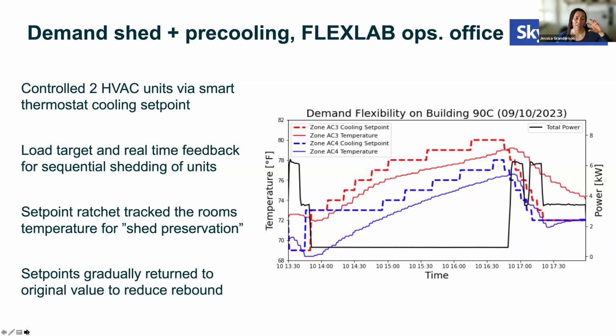So, 2 units. On the infrastructure we connected with, we went from the FDD to the smart thermostat, and we manipulated set points there through the write back feature. We had real-time feedback and an established load target, and we could sequentially shed across the units and do a set point ratchet to preserve that load shed throughout the duration of several hours. Otherwise, if you make one adjustment, you might shed for a while and then float back up as you need to satisfy the cooling needs of the space. We did a gradual return to avoid the rebound. So the data is shown on the right.